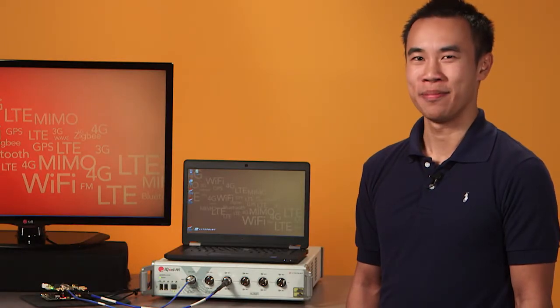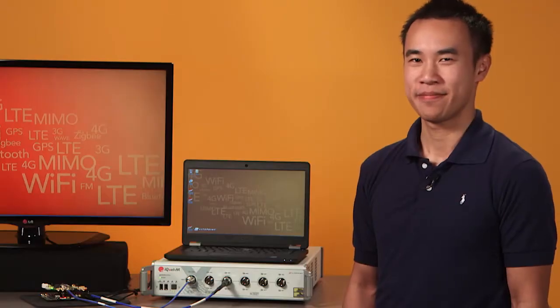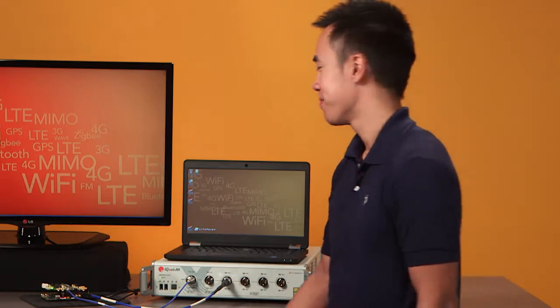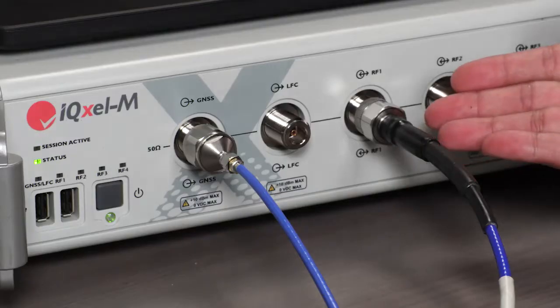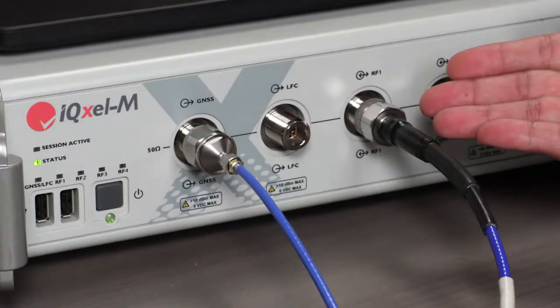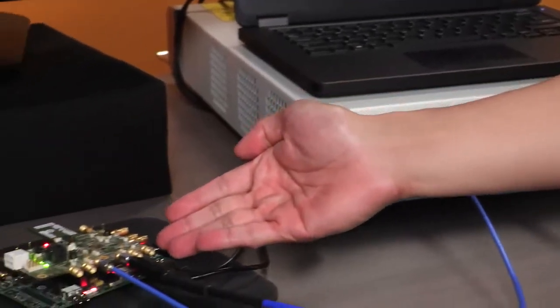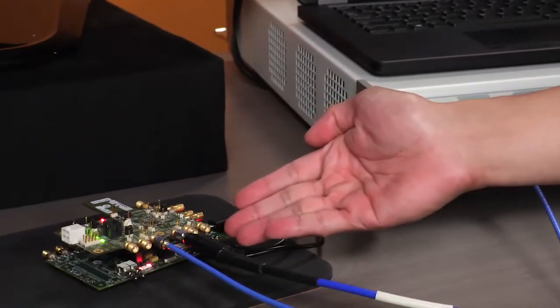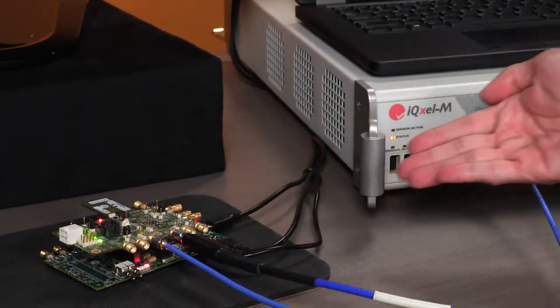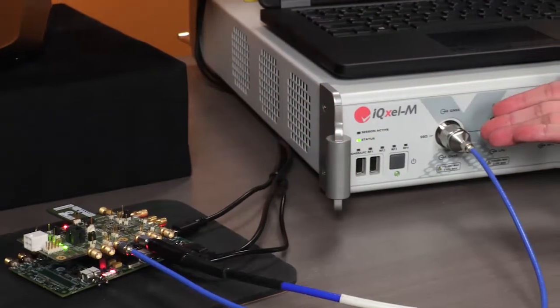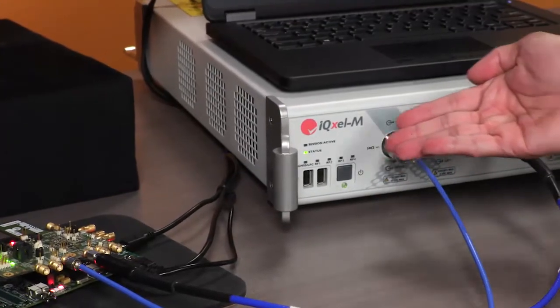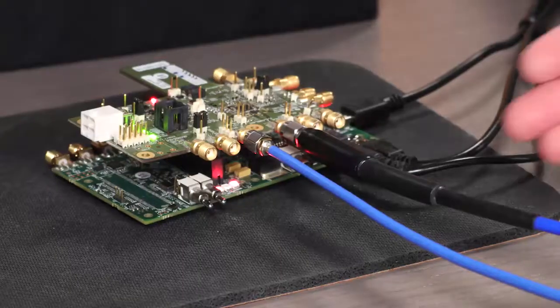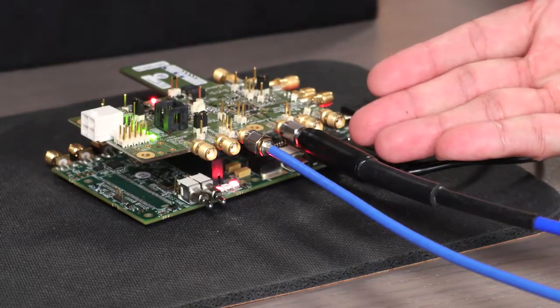Now let's see the iQxel-M in action. We'll use a typical module that has Wi-Fi, Bluetooth, and GPS. iQxel-M's RF port 1 is connected to the Wi-Fi Bluetooth DUT port, and Global Navigation Satellite System port is connected to the DUT's GPS port.